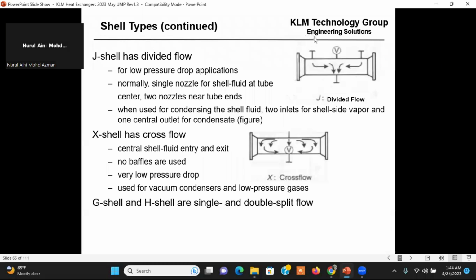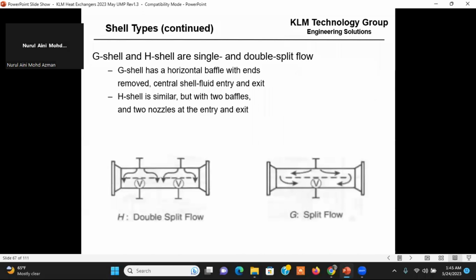J, you've got 2 inlets and it comes this way. An X comes this way. You've got central fluid entry and exit, no baffle to use, very low pressure drop, used for vacuum condensers, low pressure condensers. So it just goes in the top and out the bottom. G shell and H shell are single and double split flows. So they look like this. And so these are the types of the shells. I typically use that very first one, which is really simple. Okay.